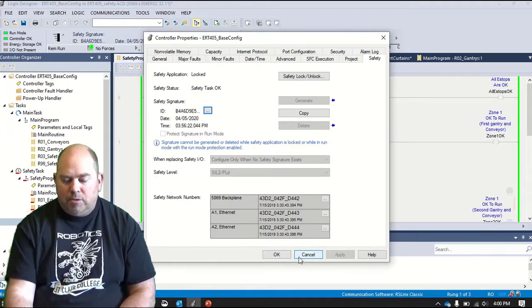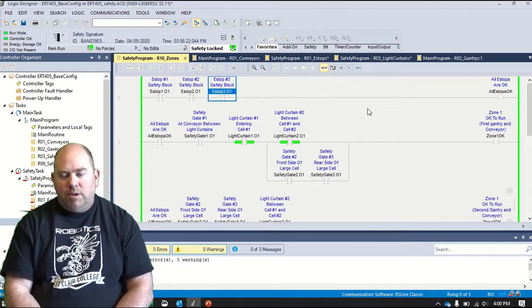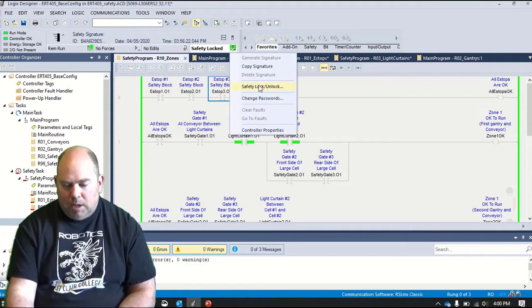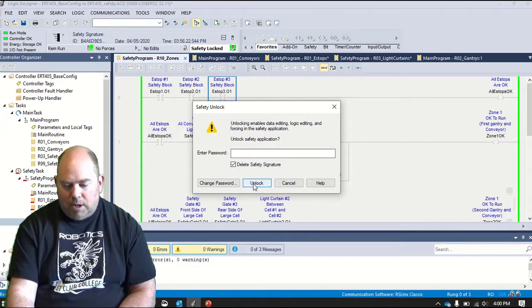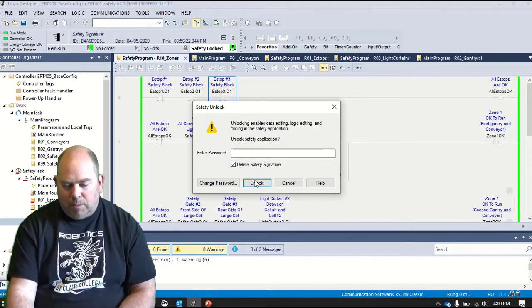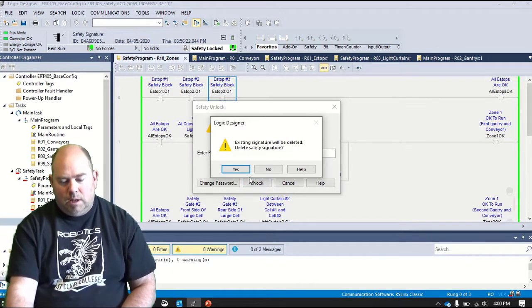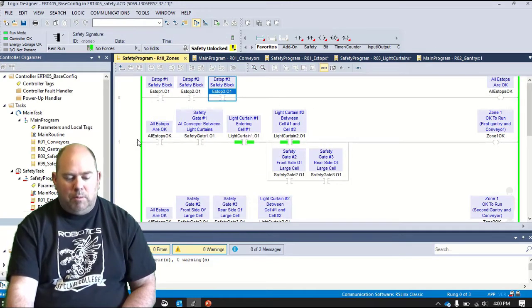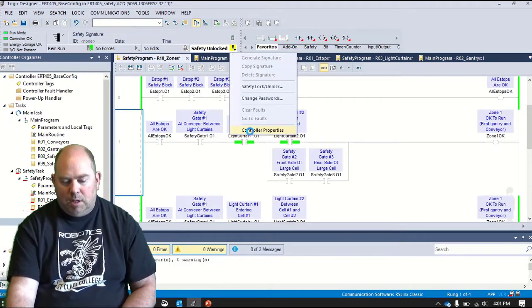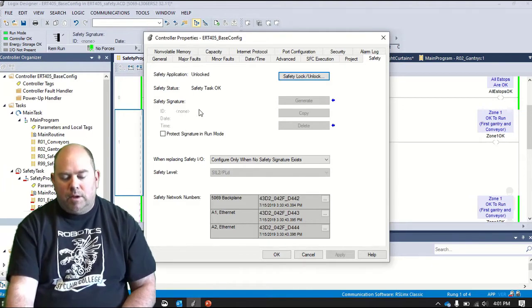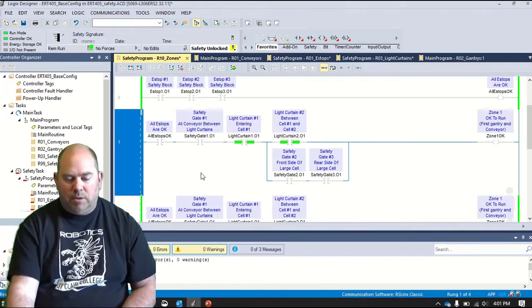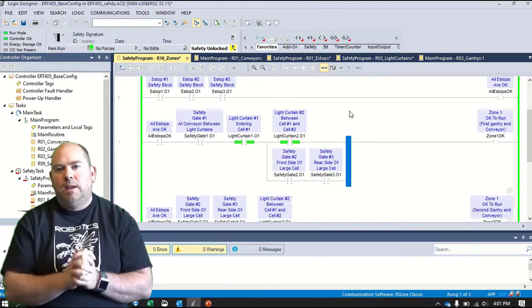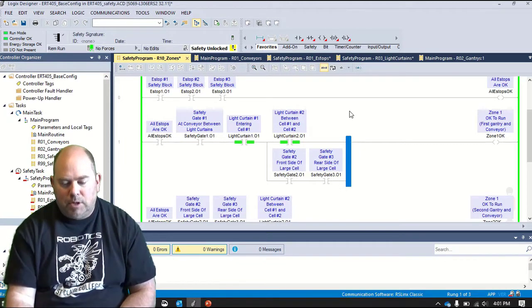Okay, so that is how we would apply a safety system to the PLC. So I'm going to actually unlock this now. I'm going to say delete safety signature and unlock. You can see if I don't put in the password, it won't let me do it. I need to put in the password, delete the safety signature, yes. Now this goes back into a mode where I can edit it. But you will also see that safety signature is now gone. Okay, so if I was to try to change this now and relock it again, I would be creating a new safety signature.